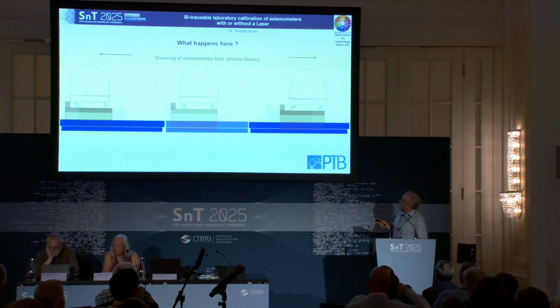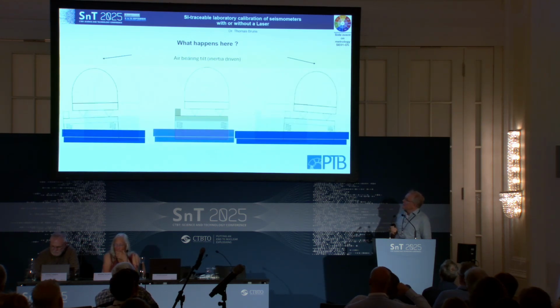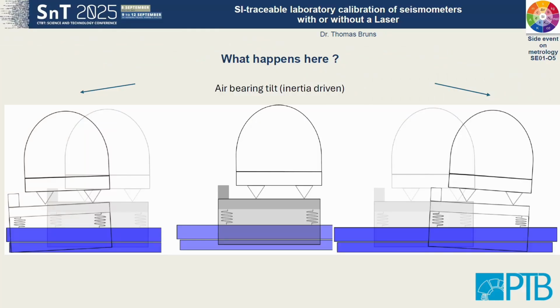The other thing that we found, and this is a property of the seismometer, so it should be included in the calibration because it's a property of the instrument. The other thing we found was a tilt, but the tilt of the seismometer was very closely the same as the tilt of the air bearing table. So apparently the source of the tilt was the air bearing table and not the seismometer, not the instrument.